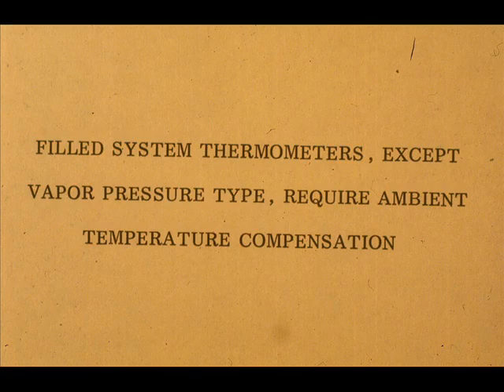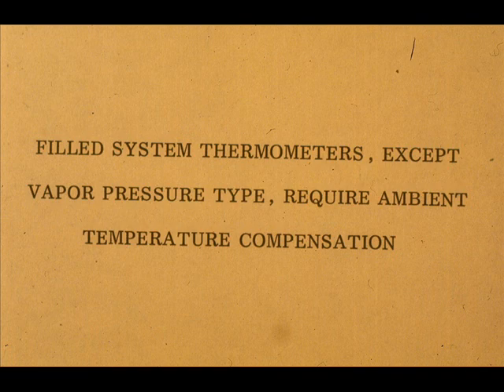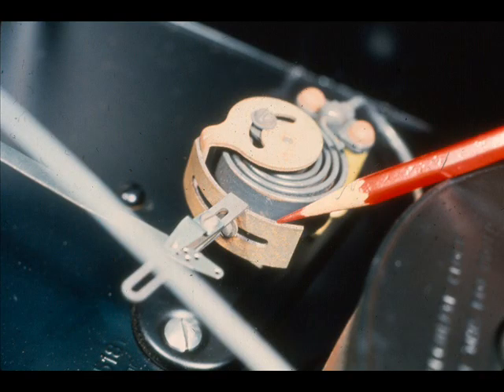Filled system thermometers, except the vapor pressure type, require some form of ambient temperature compensation. The most common form of case compensation is the bimetallic strip, like the one shown here. It counteracts the movement of the tip of the pressure-sensing device.